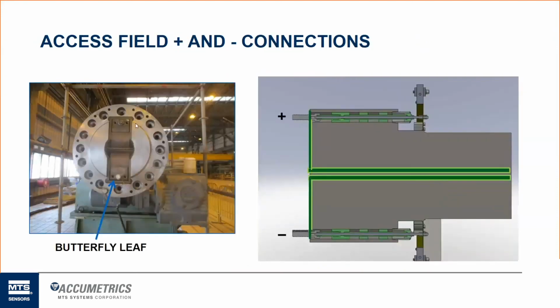So this is the end view of what the rotor has, and the exciter will have the exact same coupling, just like this. Those field voltage connections, the plus and minus, are run through the bore of the rotor itself and the exciter rotor as well, and they're broken out into what's called this butterfly leaf assembly. One of these copper bus bars will be the negative side and one will be the positive side. They're isolated from the rotor typically by G10 or G11 fiberglass material, and from each other by another piece of insulation material.